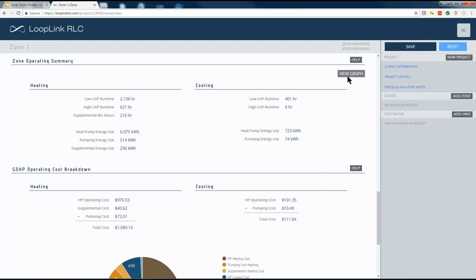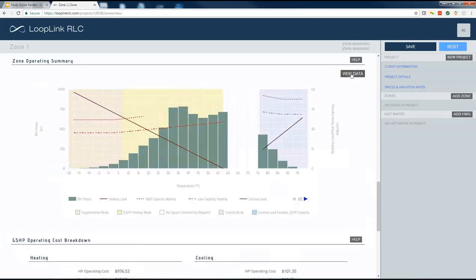But if you take a look at the bin load profile graph, you can kind of see what's going on here. The green bars here are the bins, the number of hours in each temperature range. And you can see outdoor air temperature on the bottom x-axis here, and you can see bin hours on the left-hand y-axis here, building load or heat pump capacity here on the right-hand y-axis here. So what just happened is we had a heat pump that was covering 100% of the load, so it was sized all the way out here. When we went from that 5-ton to the 4-ton unit, you can see we slid our balance point all the way back to about between a 5 and 10 degree balance point temperature right here.